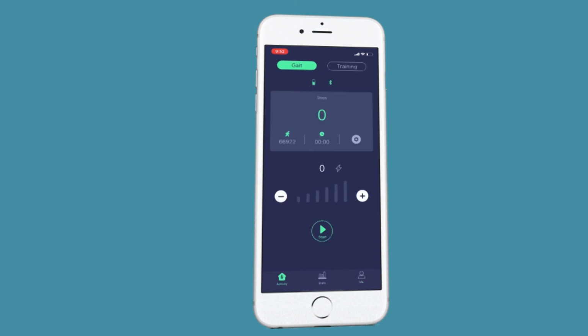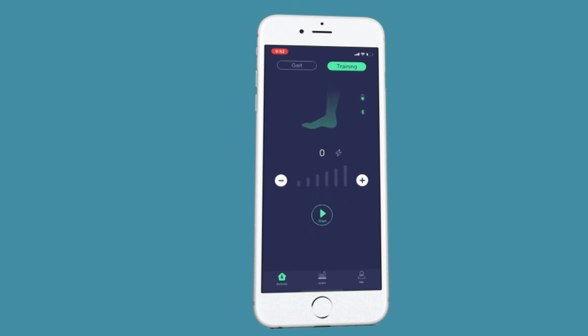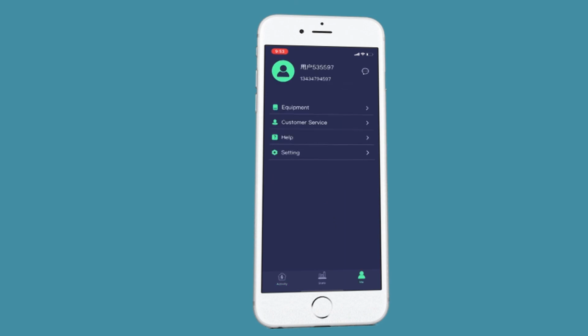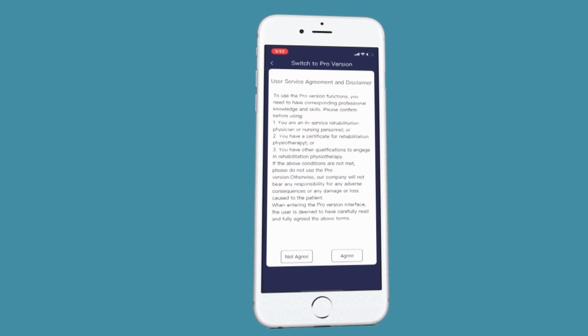And then you can quickly change to training mode, and training mode has default parameters set in. You hit start, increase the intensity to an appropriate motor response, and it takes you through a training mode. Again, you can get indications of when the stimulation is in fact firing, and then you hit stop. And again, there is not availability for the patient to go to pro mode.